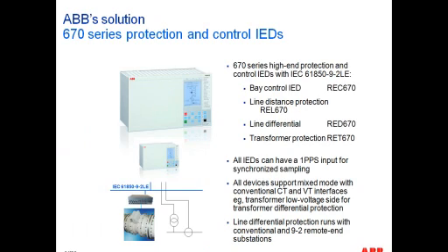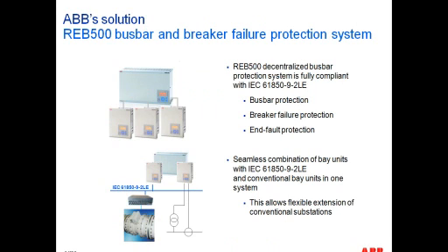So when we take a look at the different products that were involved here, we have the CP sensors, which is a combination of current and voltage sensor for GIS breakers. We have our 9-2LE merging unit, and then we have the IED 670s. In the case of the IED 670s, we have the capability of receiving current and voltage signals from both 9-2 as well as conventional current and voltage transformers, because the low voltage side of the transformers for differential protection did not have sensors connected to the merging unit. So that's why we actually had a combination of conventional currents into the relay, as well as sample values for the current contribution from the high side for the differential protection of the transformers.